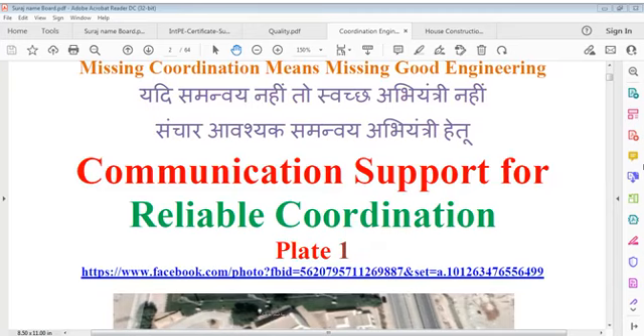Care should be taken that the proposed space for air conditioning ducts, false ceiling hanging wires, and electrical cables, trunkings and trays etc. are not encroached upon, for which close coordination of the affected zone is required. There should be no clashes at all; clashes are very serious in nature and should be resolved—that's part of technical coordination, technical work, technical interaction. The only additional cost to be borne is the cost of providing steel brackets anchored to the slab, with pipes resting on the brackets.